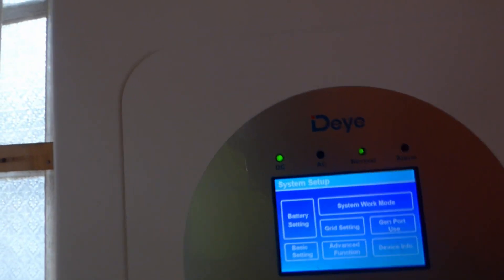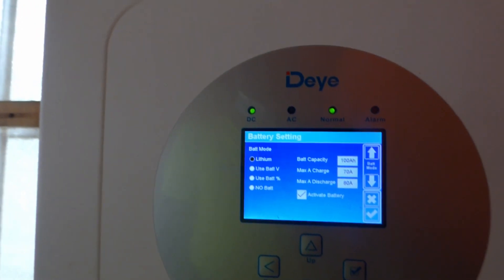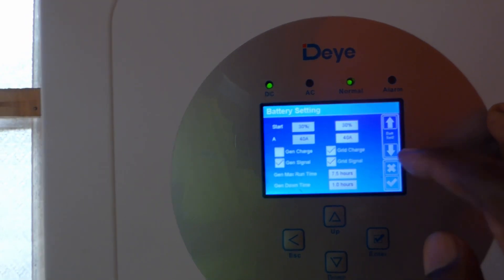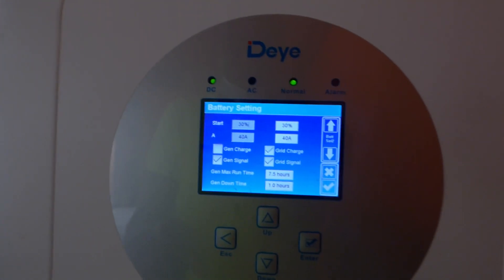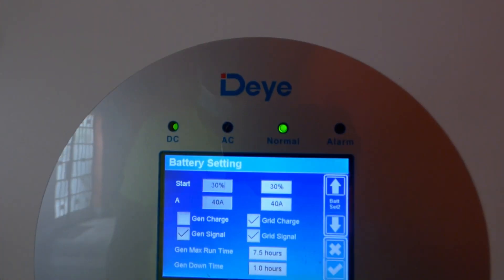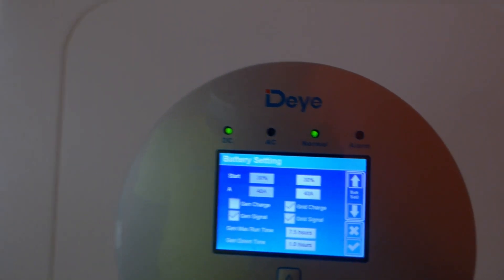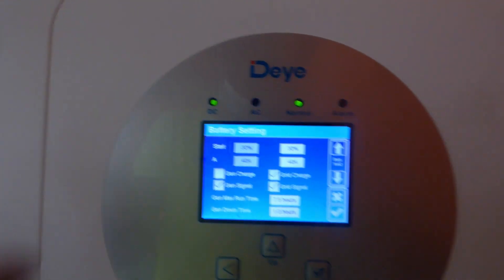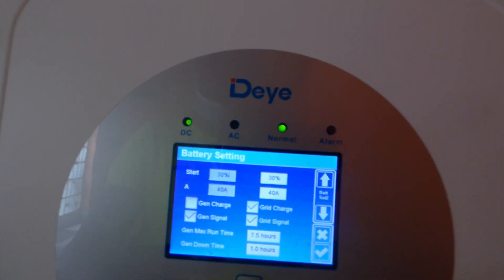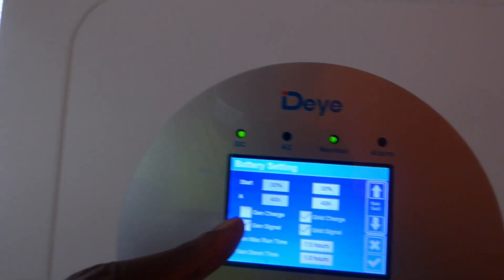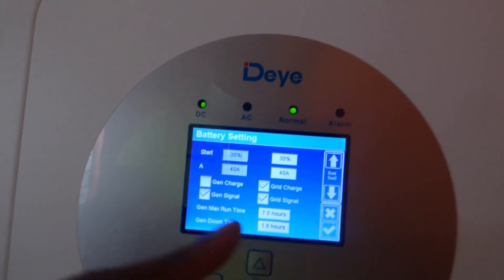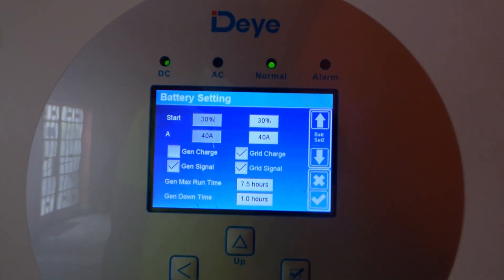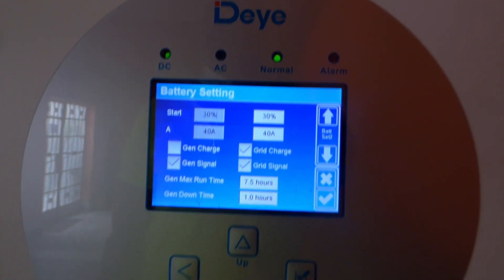We're going to go into the setup menu. First, go into the battery settings. In the battery settings, you want to use battery percentages because Time of Use is all based off percentages. Make sure you have the grid charge function turned on. Even though other settings are here, we're going to ignore them — it says start at 30%, but we can move that number higher. If you're going to use a generator, activate the gen charge and gen signal, and set the maximum hours you want your generator to run. I have it set at 7.5 hours, and generator downtime — minimum time off — at one hour.